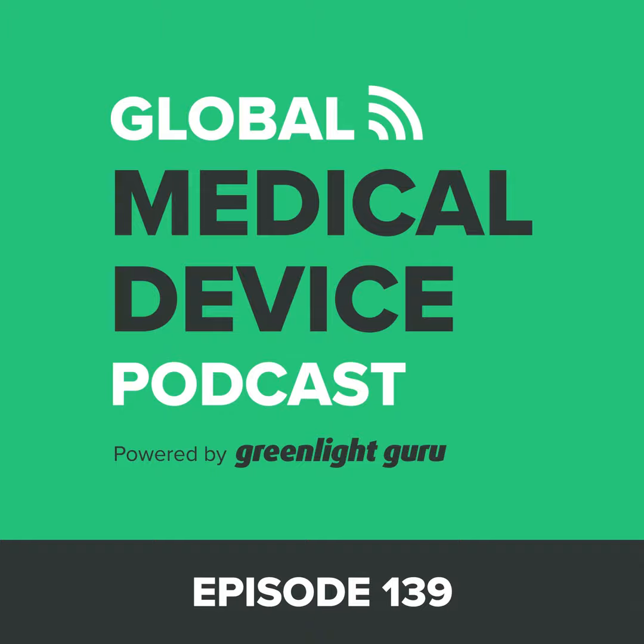The one thing that is absolutely required usually is that you at least discuss your usability through your use risk analysis in your submission, whatever submission type it may be. And which type of usability testing you have to do is based upon that use risk analysis. So you do your risk assessment. If you have no critical task with your device, then your usability testing can be pretty lean. If you have a high-risk device, you're going to have to do more usability testing.